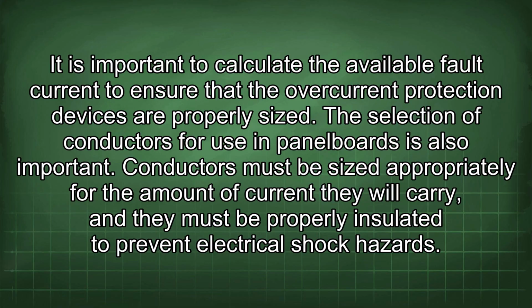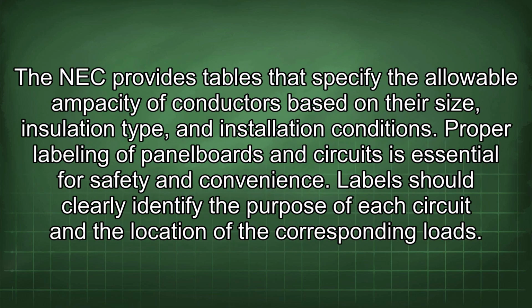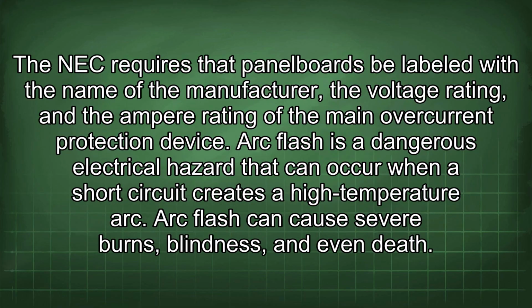The selection of conductors for use in panelboards is also important. Conductors must be sized appropriately for the amount of current they will carry, and they must be properly insulated to prevent electrical shock hazards. The NEC provides tables that specify the allowable ampacity of conductors based on their size, insulation type, and installation conditions. Proper labeling of panelboards and circuits is essential for safety and convenience. Labels should clearly identify the purpose of each circuit and the location of the corresponding loads. The NEC requires that panelboards be labeled with the name of the manufacturer, the voltage rating, and the ampere rating of the main overcurrent protection device.